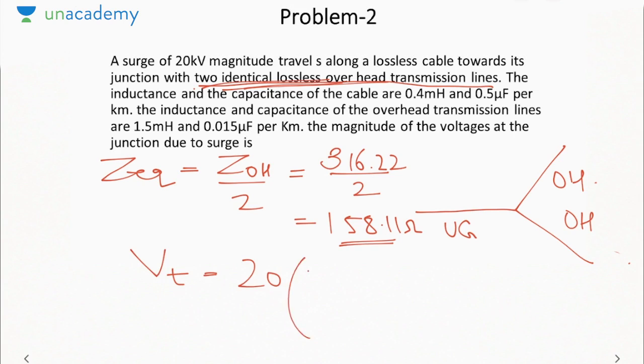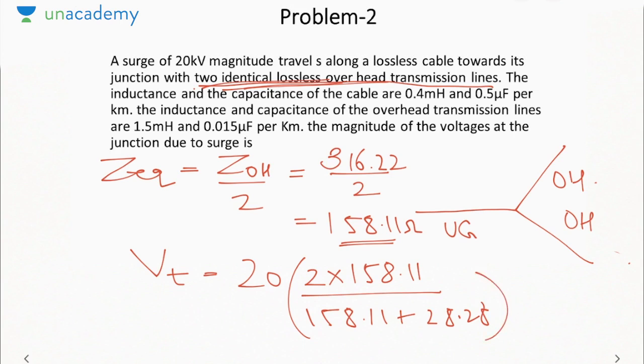Okay. Now to find the voltage at the junction, we need to find transmitted voltage, which is incident voltage 20, 2 into load impedance 158.11 over load impedance plus ZC. Now since it is traveling from a medium with low impedance to a medium with high impedance, the magnitude of the surge will increase. It becomes 33.93 kV. Okay, so surge voltage is increasing since now it is going from a low impedance cable to a high impedance overhead transmission line.